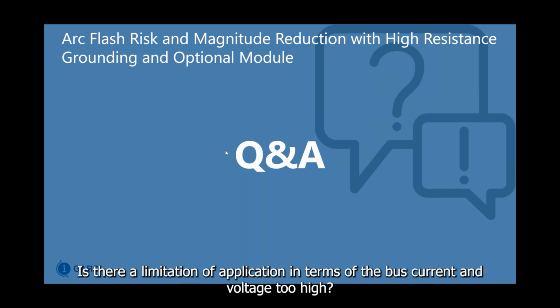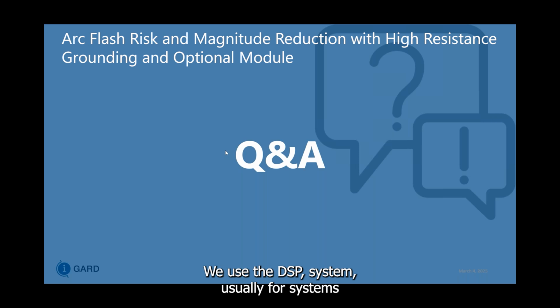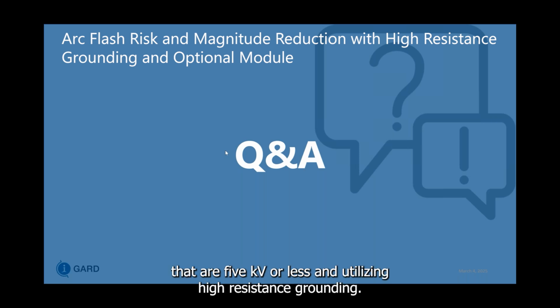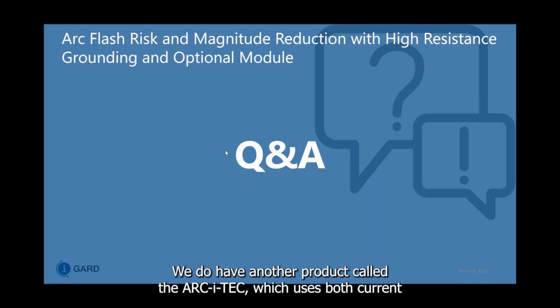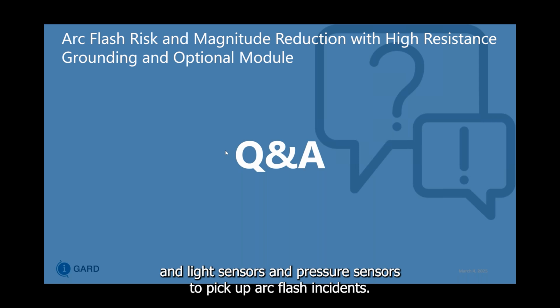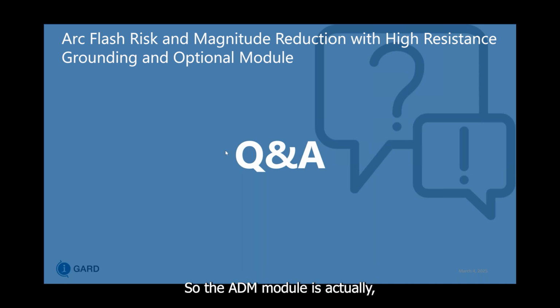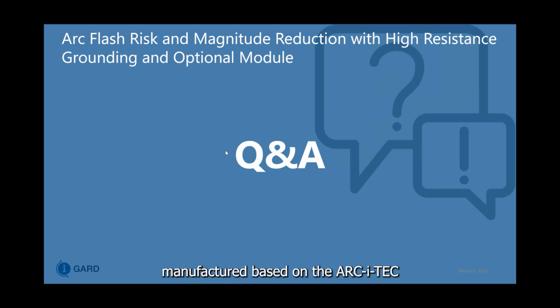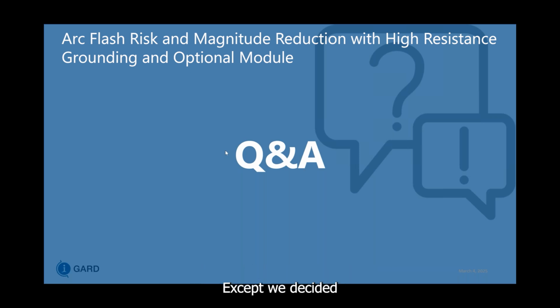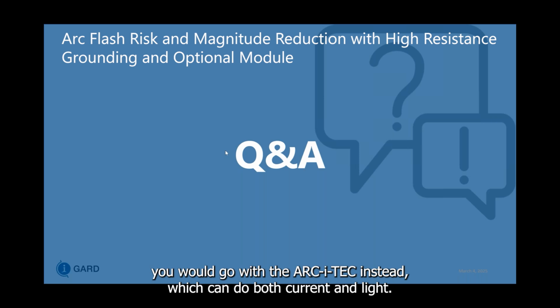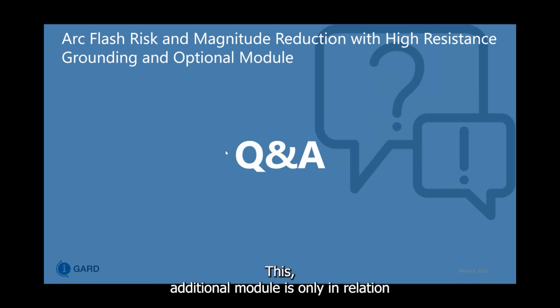Is there a limitation of application in terms of the bus current and voltage being too high? We use the DSP system usually for systems that are 5 kV or less and utilizing high resistance grounding. We do have another product called the ARC-i-TEC, which uses current, light and pressure sensors to pick up arc flash incidents. The ADM module was actually manufactured based on the ARC-i-TEC, except we decided to only use light sensors. Can this be used in low resistance grounding? I suggest that for low resistance grounding you would go with the ARC-i-TEC instead, which can do both current and light. This additional module is only in relation to when we have high resistance grounding.